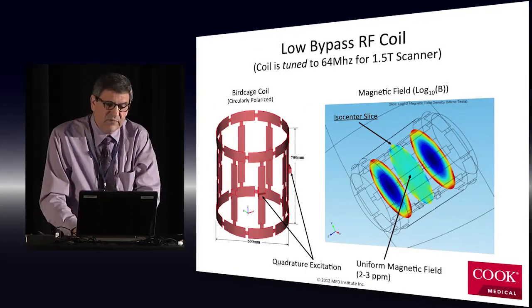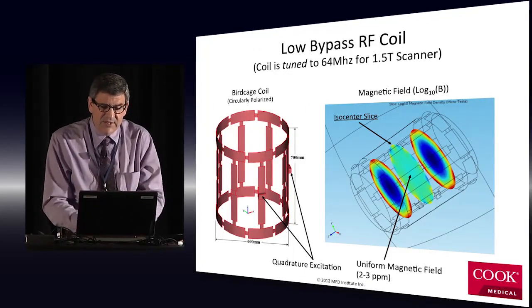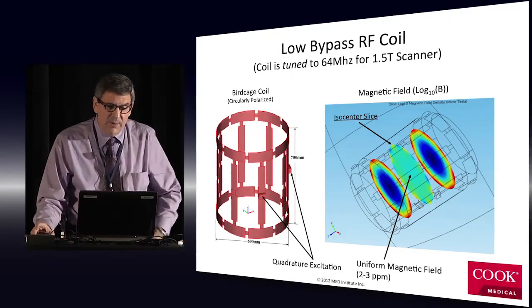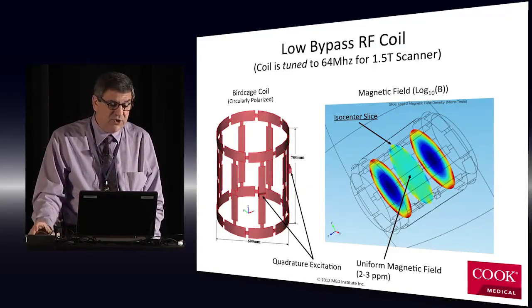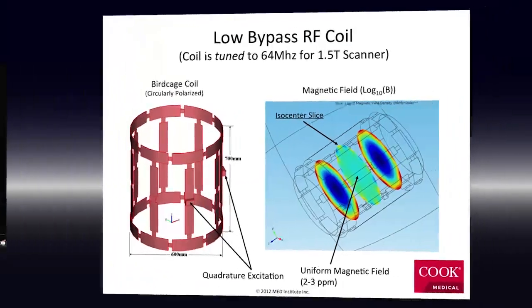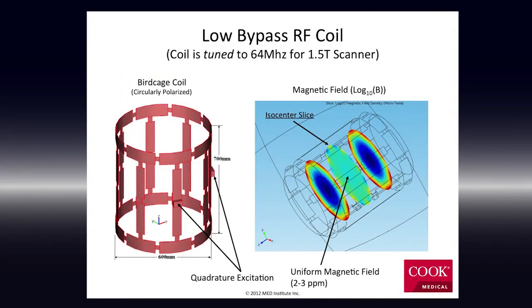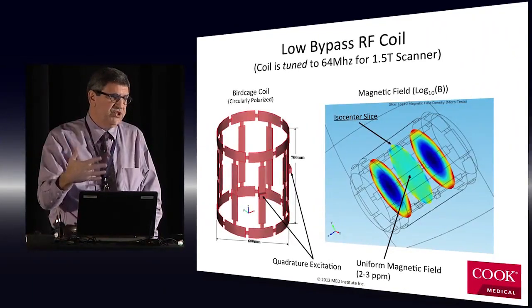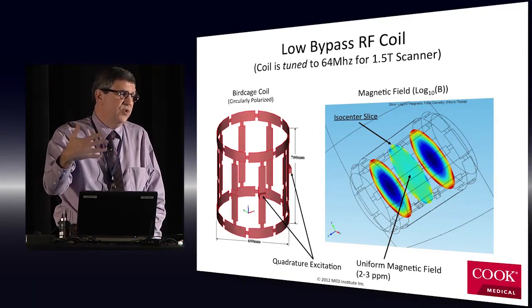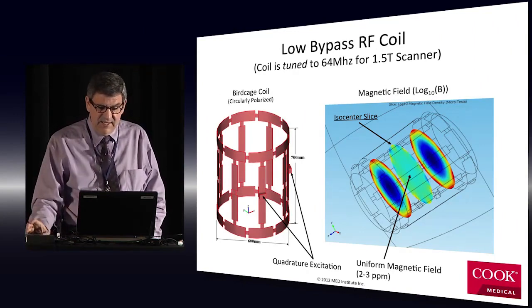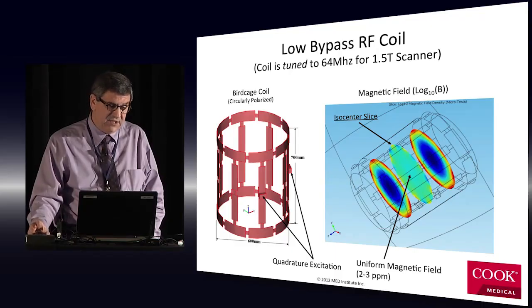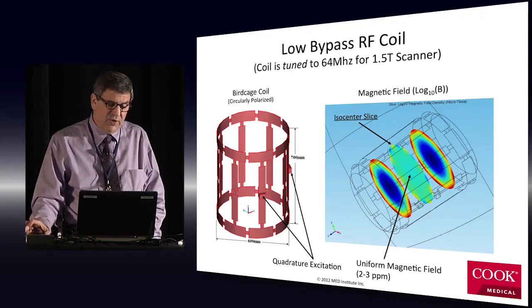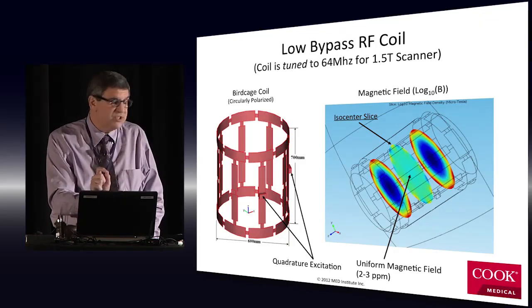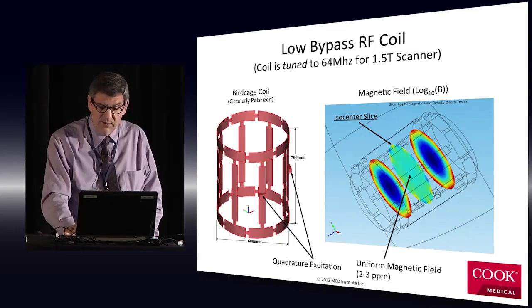Okay, so very quickly here, how do we generate this RF field? Well, we create a birdcage coil, which is fed in a quadrature fashion. Voltage is applied to these ports 90 degrees out of phase. They're 90 degrees displaced in space. And the idea is to create this uniform magnetic field in the center of the scanner. Okay, this is what the people need in order to produce good scans, a very uniform magnetic field at the isocenter or near isocenter of the scanner. And sure enough, the magnetic field that we calculate by building this in COMSOL gives us a 2 to 3 parts per million variation of the uniformity, which is acceptable and is practically acceptable and measurable.